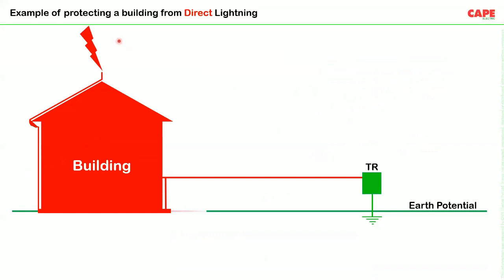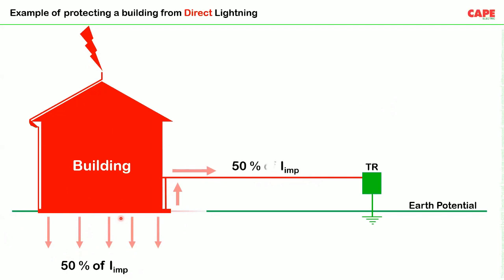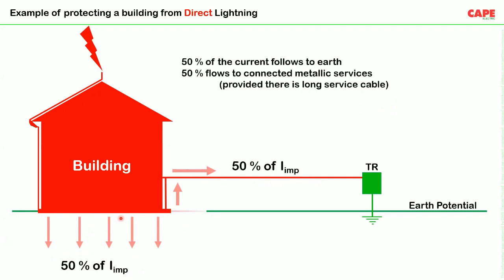building. Now imagine your building has lightning protection and perfect equipotential bonding. There is an SPD at the incoming, with equipotential bonding between the earth and the incoming line. Everything is safe. IEC 62305 part 4 says that out of the 100% current coming from the lightning, approximately 50% goes to earth through the earth termination system, and 50% of the current is diverted through the connected metallic services. Metallic services are, for example, metal water pipe, metal gas pipe, electricity supply, 3-phase and the neutral or the PE conductor. Then you have a telephone line and so on.